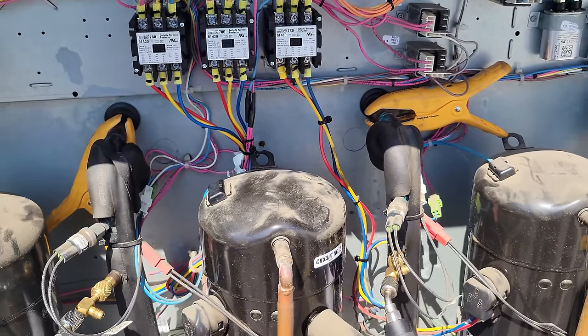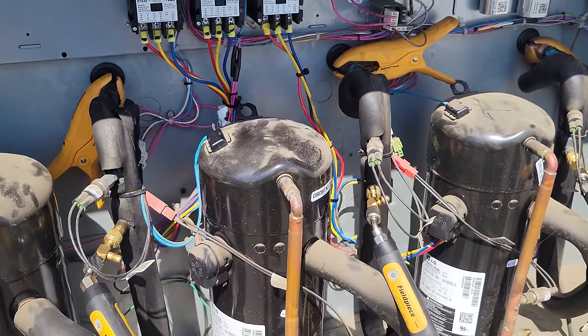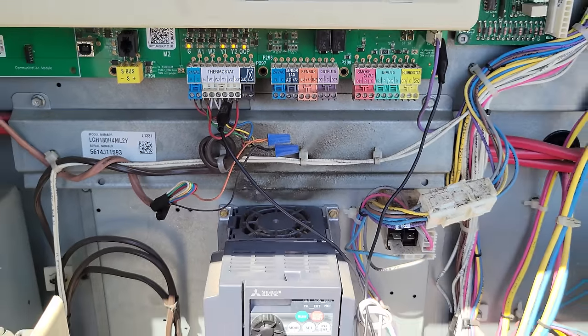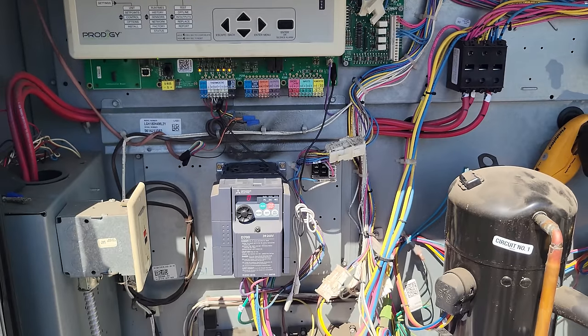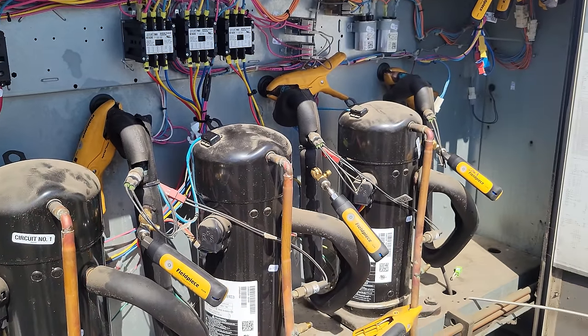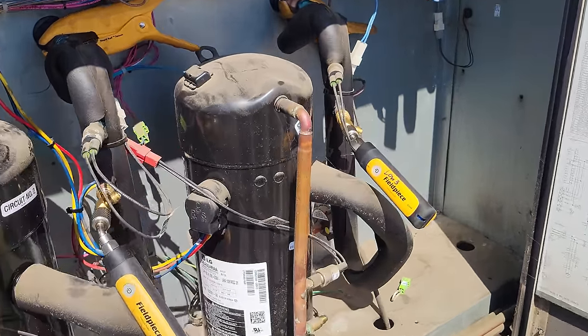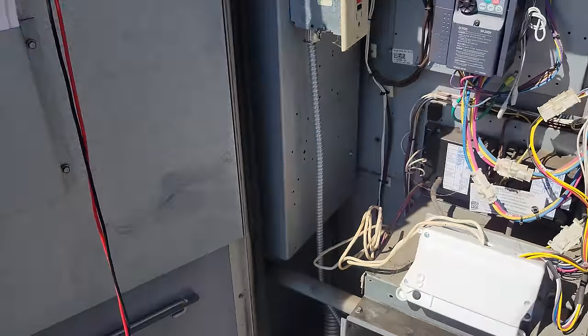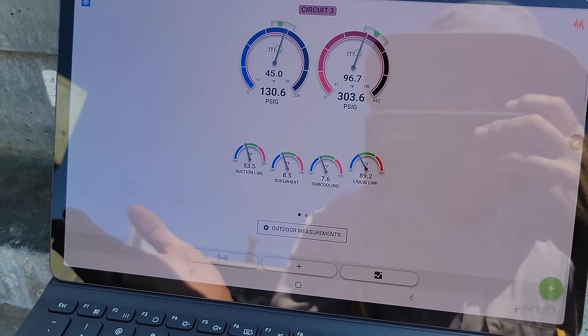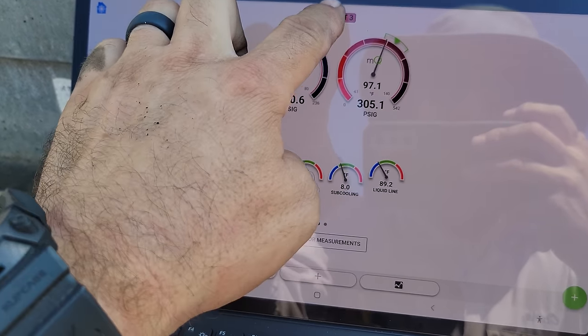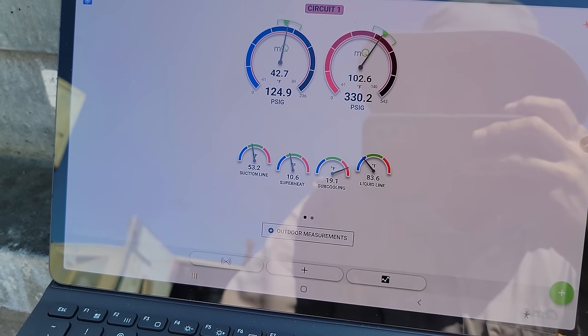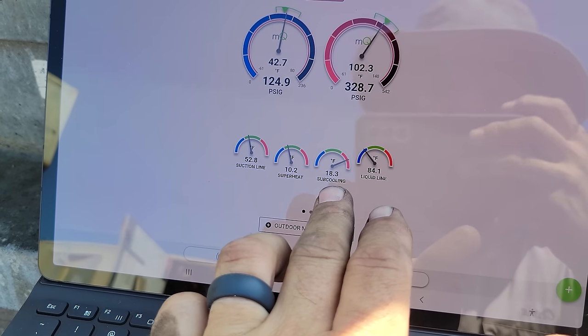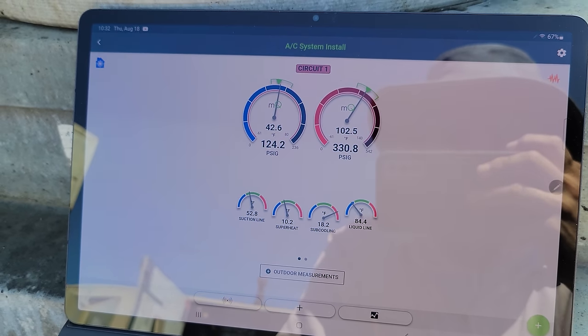No harm, no foul — I caught it. Let's turn it on and see what else happens. I still have a full call for cooling jumped out. We've got to wait for it to start up through the delay. One, two, three — all three of them running. Third stage: again, it just turned on and it's not looking bad. Let's go back to first stage. I still haven't done the dryer check on that first stage because I want to know why that subcooling and head pressure was going up so high so quickly. Evaporator temperature looks decent and superheat is being controlled by the TXV. We're looking pretty good except for that first stage.